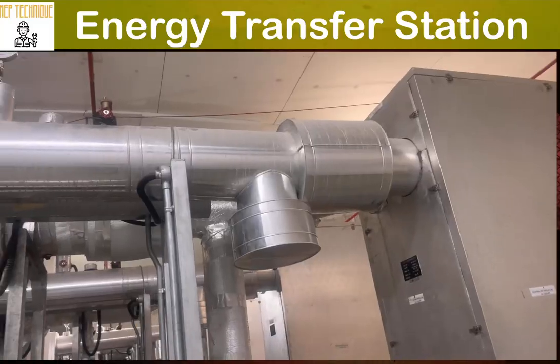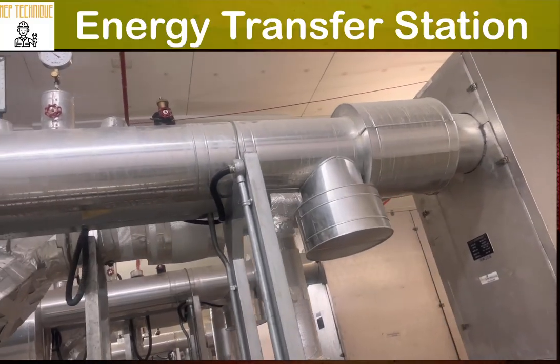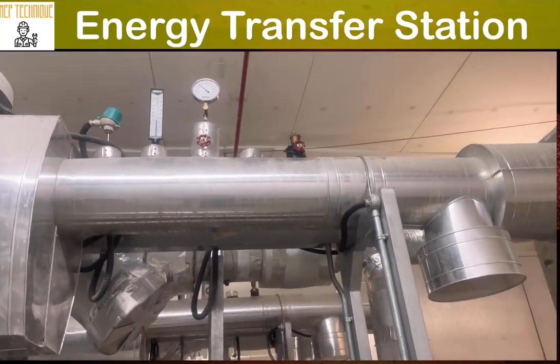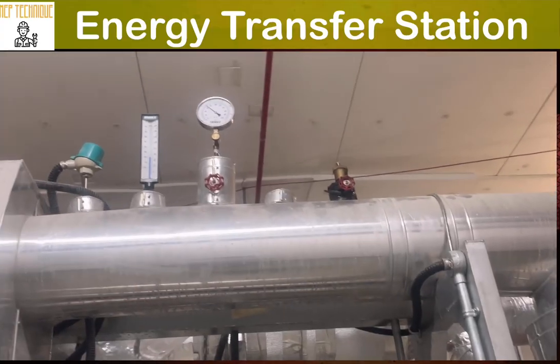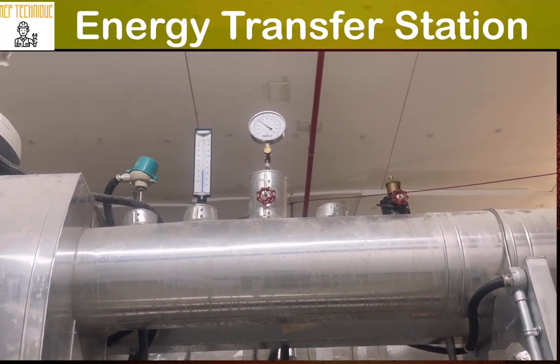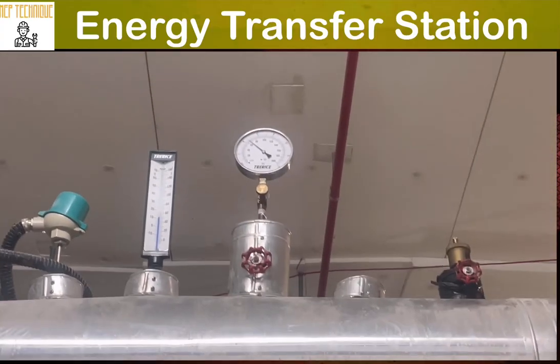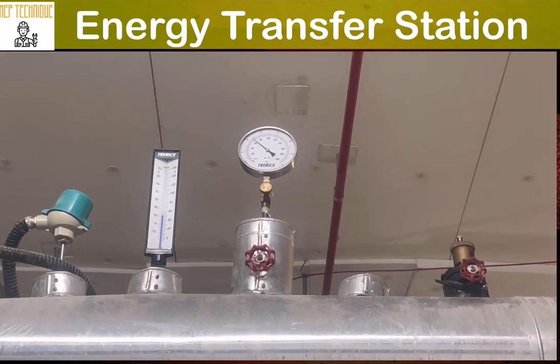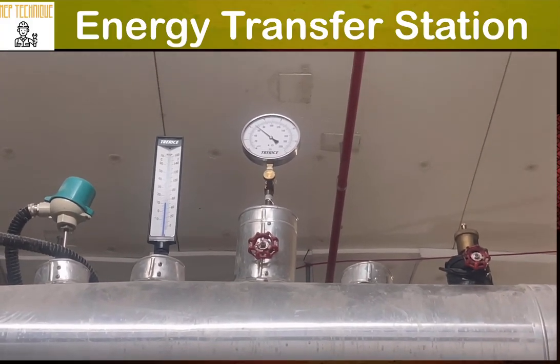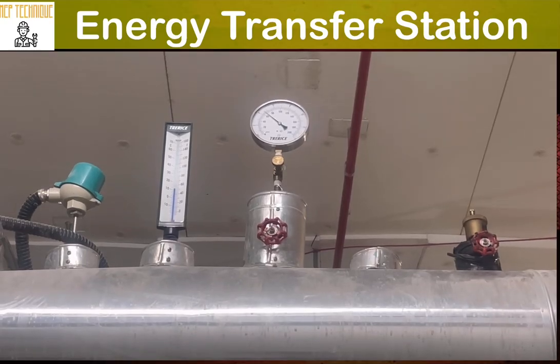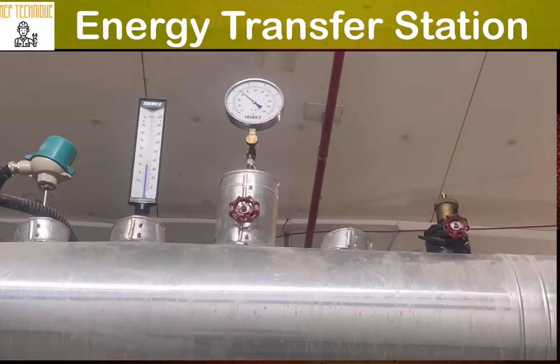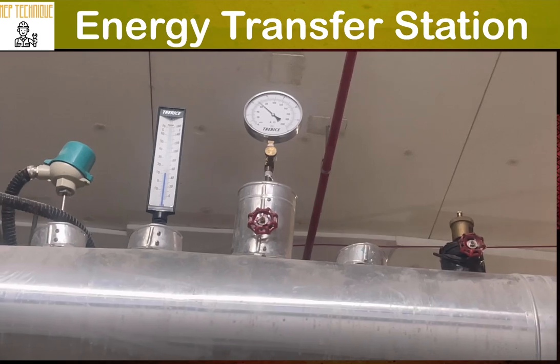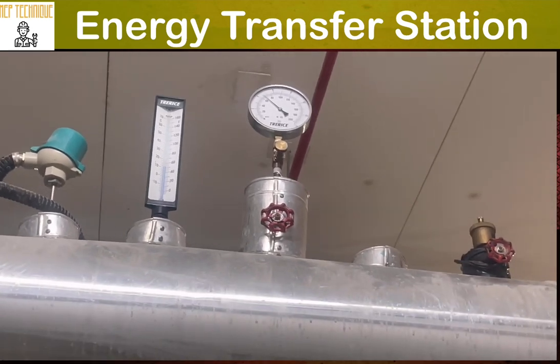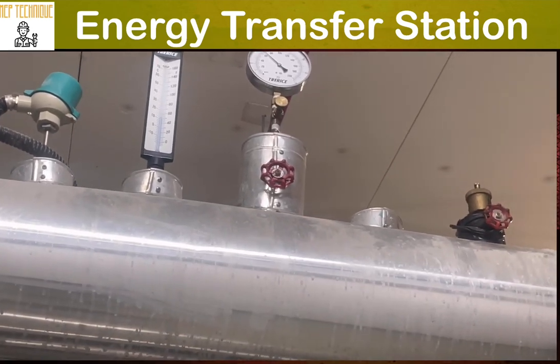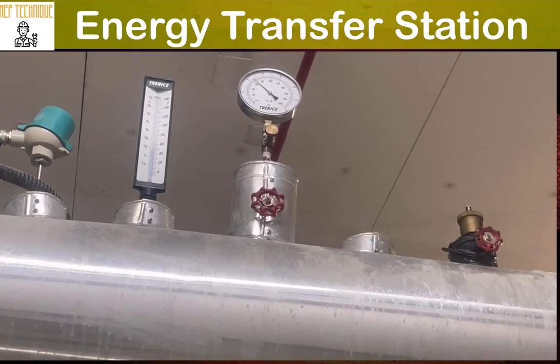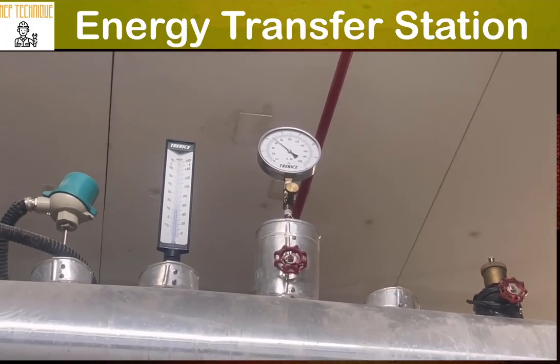Then this is the return line from the heat exchanger. Here also you can see one pressure gauge and a temperature gauge. You can see the temperature and pressure. The temperature is almost 10.2 degrees Celsius, whereas our supply temperature was only 4.4 degrees Celsius, and the pressure is more than 60 psi. The inlet pressure is also about 60 psi, with a minor difference.